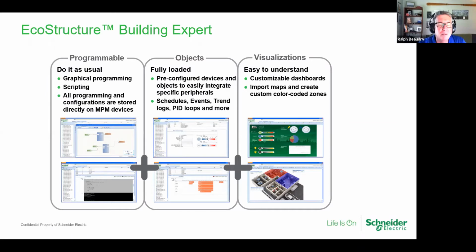Once you get on it, there's a file tree on the side. It allows you to pull in pre-configured objects, which for you would typically be an SE8000 of some kind. So an 8650, an 8350, you bring it in, all the points are there. And then you put in the communication credentials for the gateway. So you tell it what PAN ID, the personal area network it needs, what channel it's communicating on. We recommend channel 25. PAN ID is a unique number. So if you have multiple gateways on a site, you're going to have multiple PAN IDs. But if you use channel 25, you can use it on all of the gateways now.